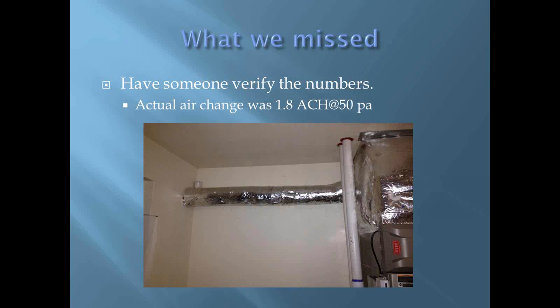It's amazing. So what's causing the house to be negatively pressured? The stack effect. Even in the summertime, you still have heat driving up. And then I talked about the leakage behind the drywall. So those are high leaks. And so the house is leaking, but in the new houses, we're sealing everything. We're sealing the bottom plates and all the penetrations, so there's no place for air to come into the new house.